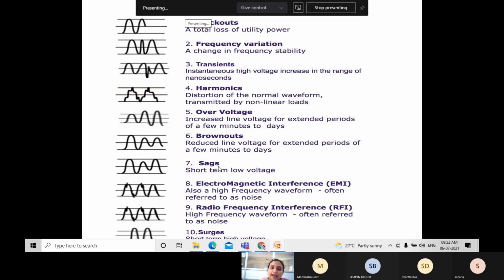Okay, it is decreased suddenly. Next is sag. Sag is also a short-term low voltage. A brownout is continuous, lasting for extended periods of a few minutes to days, but a sag is only for a short duration. The voltage is normal, for example 230, but suddenly it decreases to 120 or 150, and that too for only a few minutes or a few seconds. After that it returns to normal voltage. That is what a sag is.